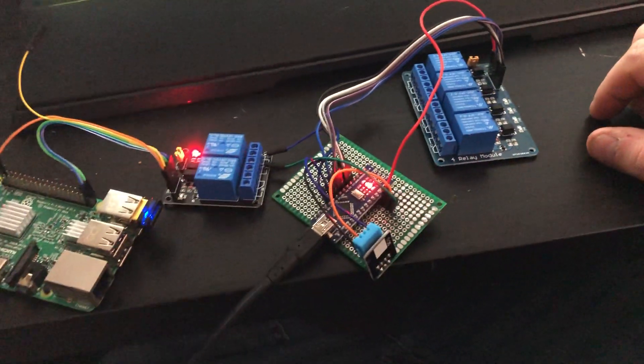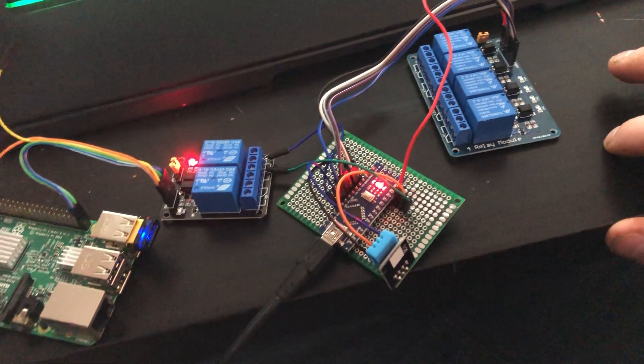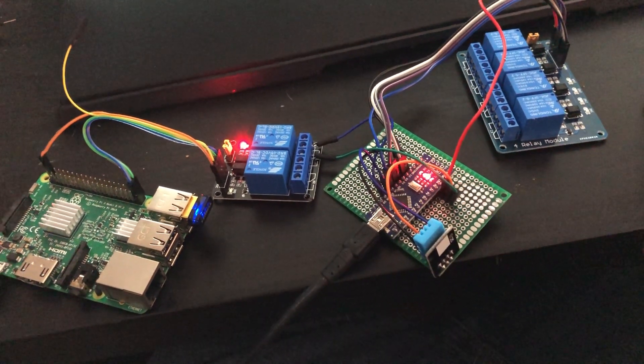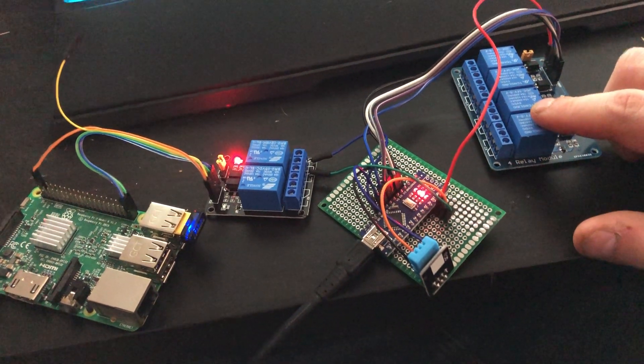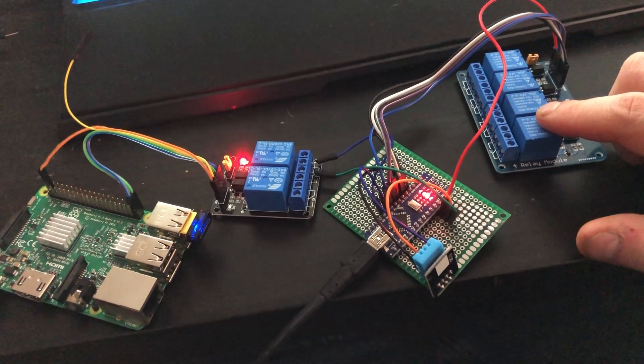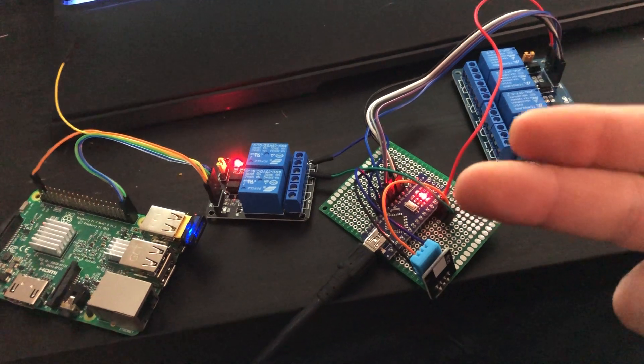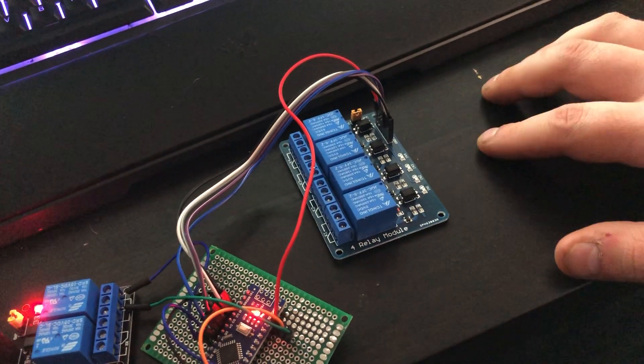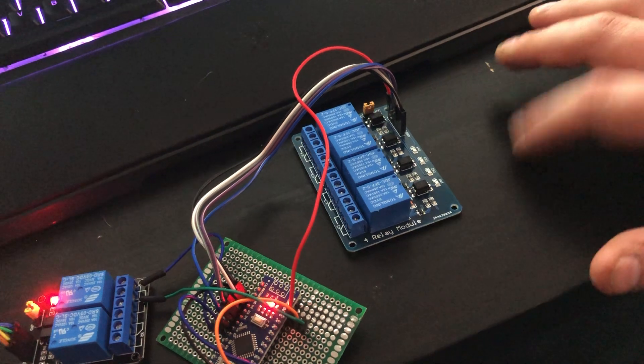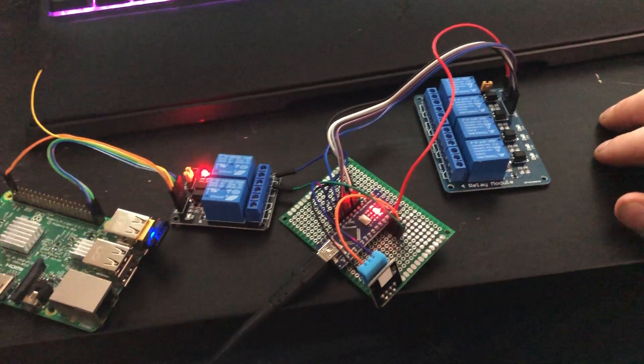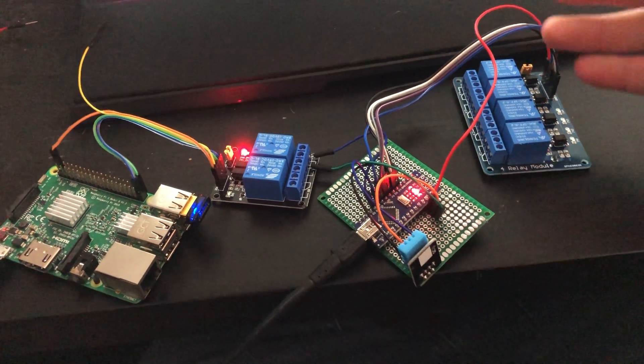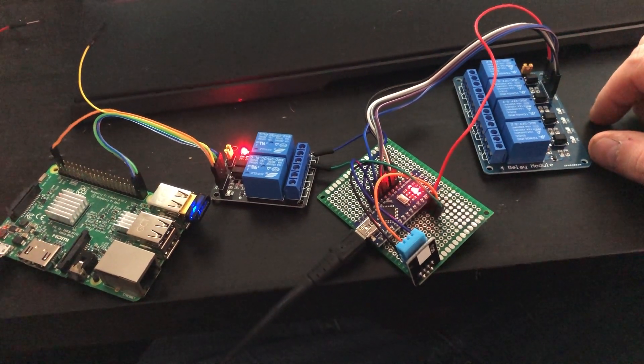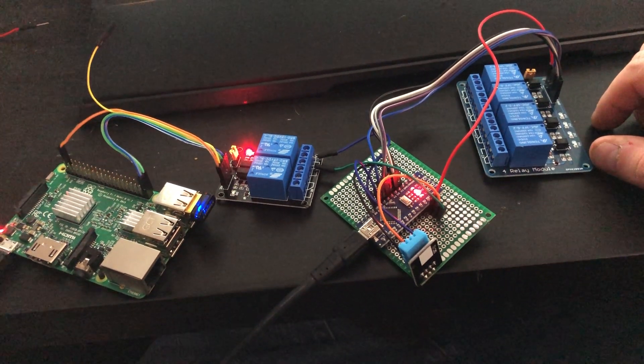So between this and the 712, I have a method to fully manage my generator start stop based upon the load, just as if I'm running AC or if my batteries are dead. And I have a method to cut off all my loads of the batteries at a critical depth of discharge with the Victron unit. So all together, I basically have, pardon the cringe here, but a Prius type hybrid generator system, which I think is really damn cool.